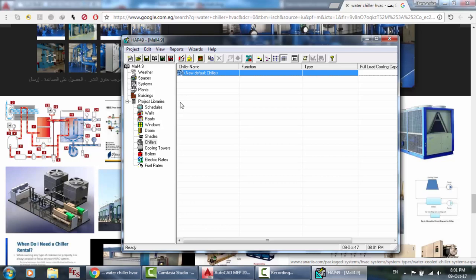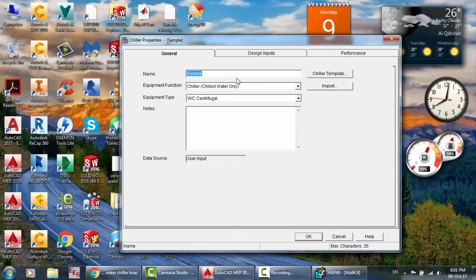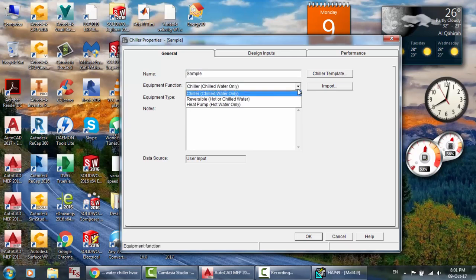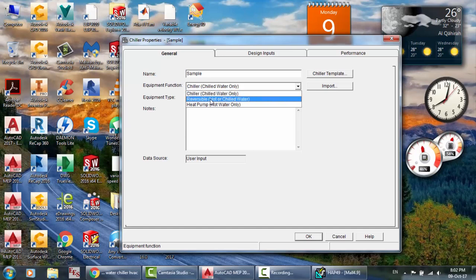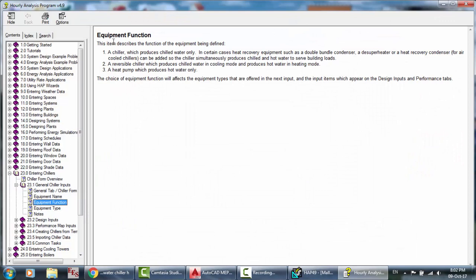If your total cooling load is 500 kilowatts and you need two chillers, you have to define a 250 kilowatt chiller — not the total. Here is the name field for the chiller — name it as you want. For equipment function you can choose: chilled water only for cooling, reversible hot or chilled water for heating and cooling, or heat pump for hot water only. You can click F1 for more details.